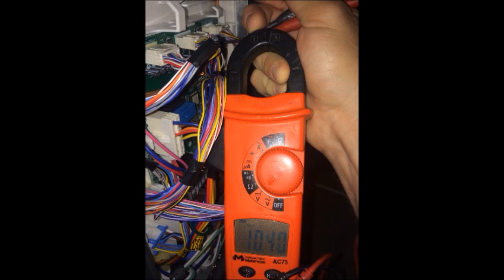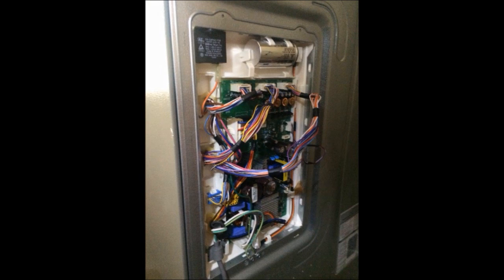So we'll follow that up with our second test, which is testing pin 1 and pin 2. What we're looking for here is 12 volts or above, so anytime we have a meter reading below 12 volts, we're going to be interested in this. If you look at the meter, we'll see it is 10.43, so we're below 12 volts. In this instance, our correct diagnosis would be to replace the main control board. So that whole control board right there would get replaced, and that will cure the fan error and get the refrigerator back up and running.